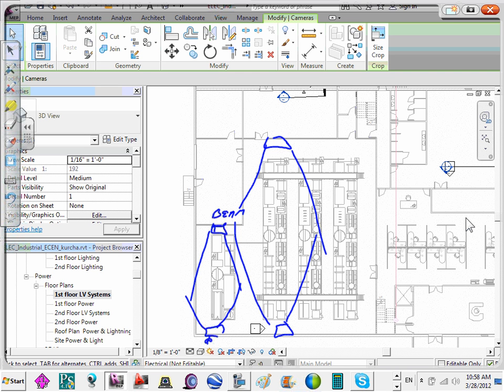Those are extended receivers. Yep. Transmit and receive, yep. It's just a single beam. We have a lot of problems in here with beam detectors. If there's skylights up here, as the sun comes across, you're going to get reflections off the lights, which can interfere with the way it's bouncing off of all the particles in the air. Dust can be a big problem.